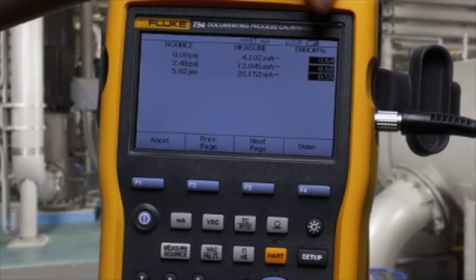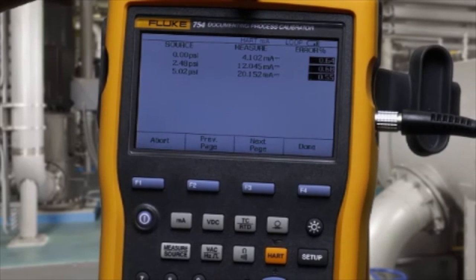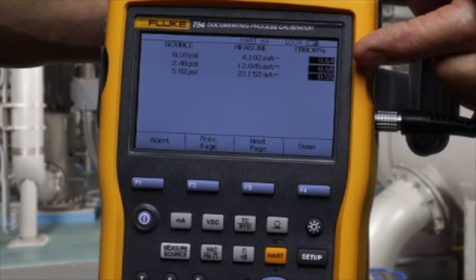If the found milliamp value deviates too far in value and the errors are greater than the test tolerance, they're flagged in a reverse video indication.